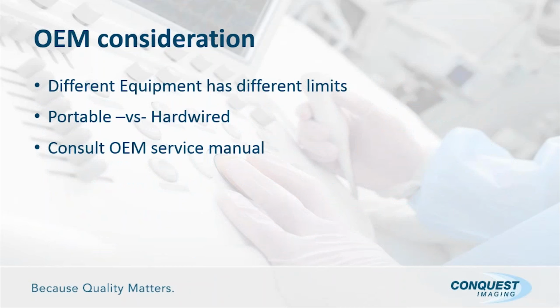When we're talking about multi-modalities, it's really important that we discuss a few factors. Different equipment has different limits. Some of the specifics I'm going to talk about today are going to relate to ultrasound limits. But if you're talking X-ray or portable X-ray, for example, they'll be significantly different from what we encounter during ultrasound. So you're going to have to really find out what kind of equipment you're discussing. You're going to have to go to the OEM service manuals and dig into what their specific requirements are. Also, is it a portable system versus hardwired? There are different requirements for those. They specify what the requirements are if they're portable versus hardwired. That's all in NFPA 99 also.